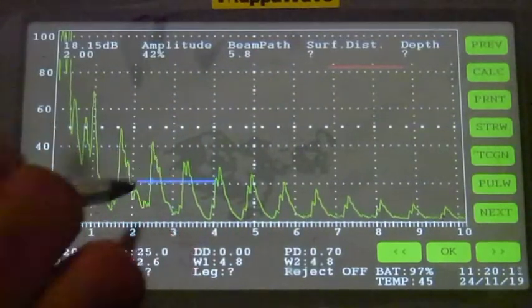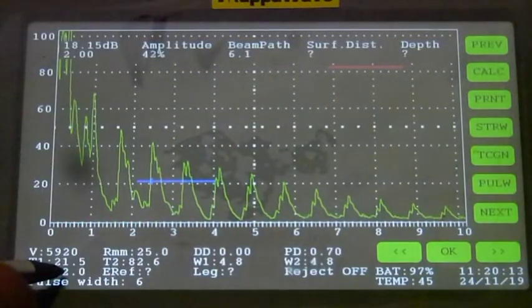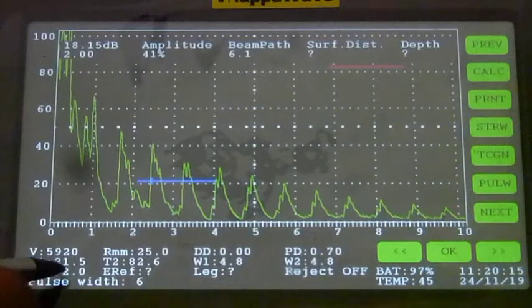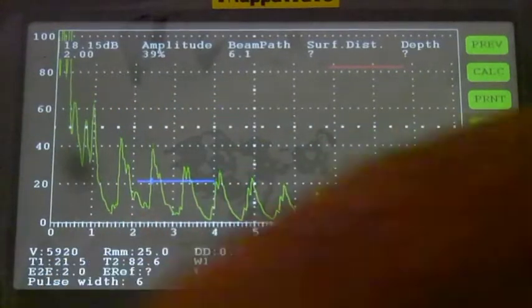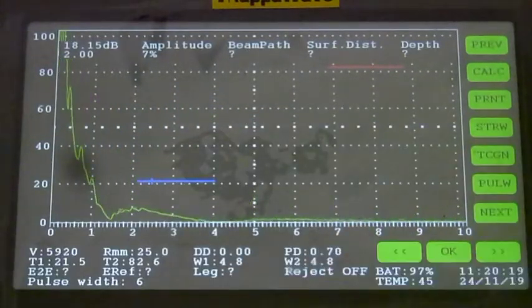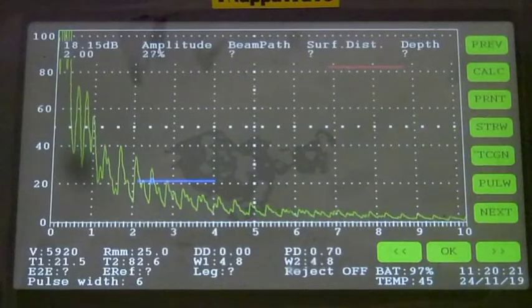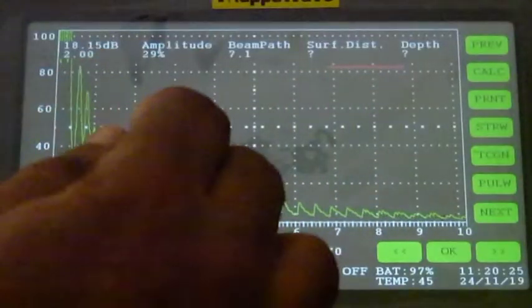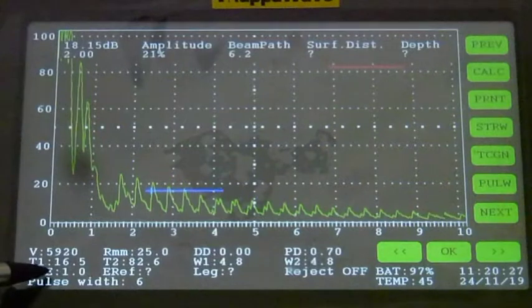We are on to something lower in thickness. This is 2 millimeters in thickness, so it gives you an echo to echo value as 2. We are using a normal beam probe here. I'm on to the last thickness, this 1 millimeter, and this echo to echo value gives you 1 millimeter.